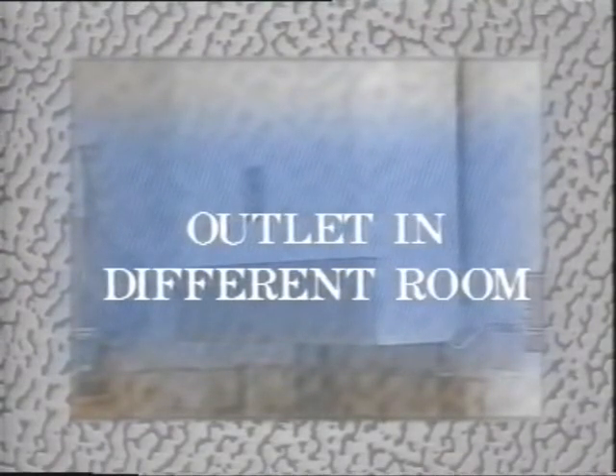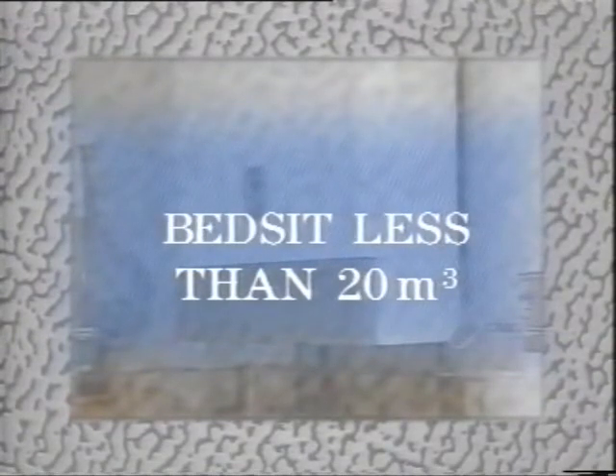They'll need a flue if they're serving more than one outlet, the outlet's in another room, they're likely to be used for more than 5 minutes at a time, the volume of the room they're in is less than 5 cubic meters, or if it's a bedsit, less than 20 cubic meters. And if the heater's in a room which has a shower or a bath in it, the flue system must be room-sealed only.